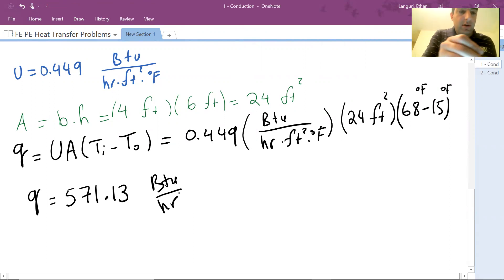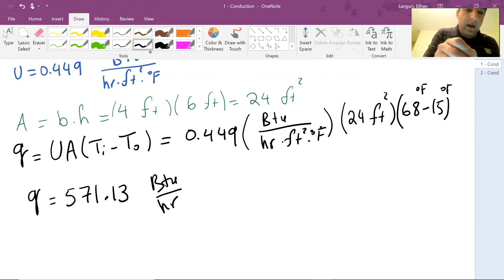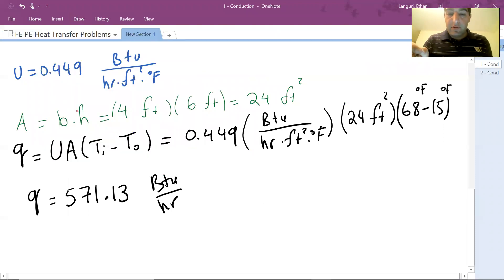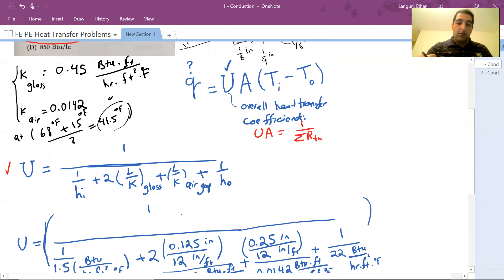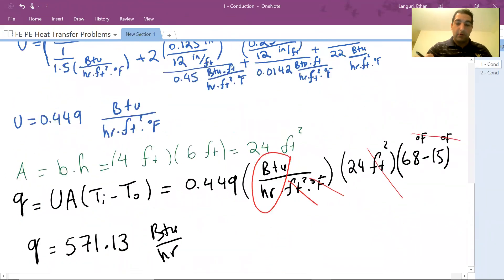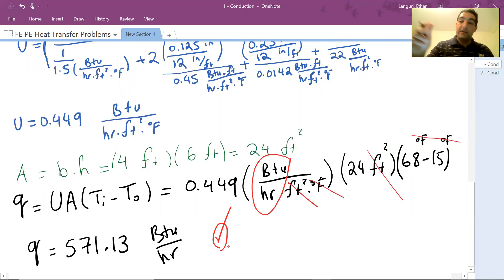So you can quickly double check your units since you have a unit. Let's do it quickly together. Foot squared and foot squared cancel out each other. Fahrenheit and Fahrenheit cancel out each other. All you have is BTU per hour, 571. So let's go back. 570 is very close. So the answer is part C. I go back to this in case you want to look at this. But this is my final answer. We'll stop here and we'll do more questions like this in next videos. Thanks.